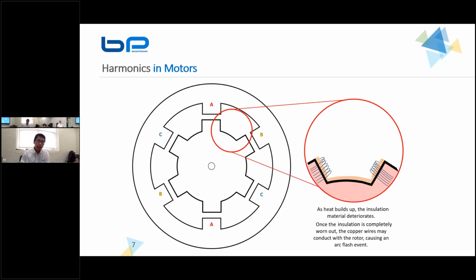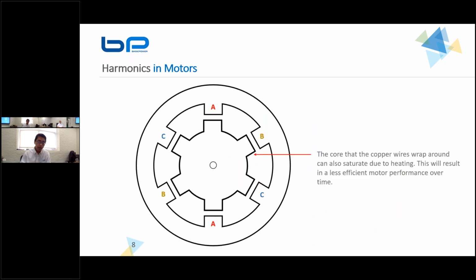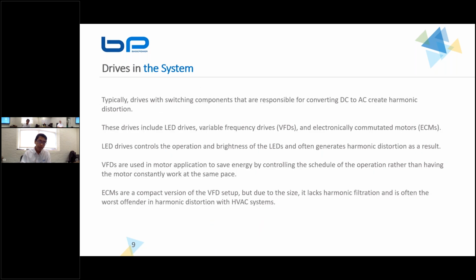Now, this stuttering can cause the insulation material within your motor to start wearing away, and that's when you get an arc flash event that can short and cause deteriorating damage to your motor. This heating can also saturate the core itself and not just the windings. This will help explain how it affects the actual motor. It will deteriorate the operation and efficiency because of the heating.